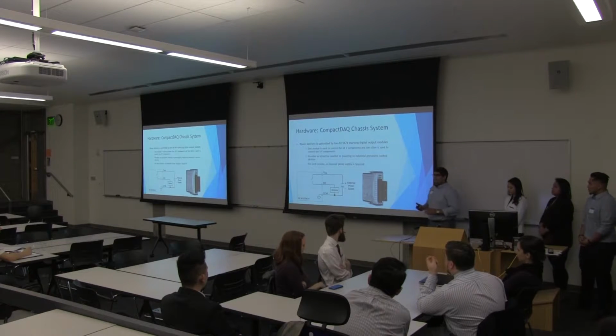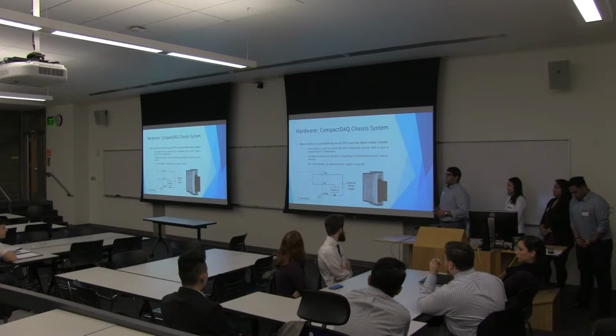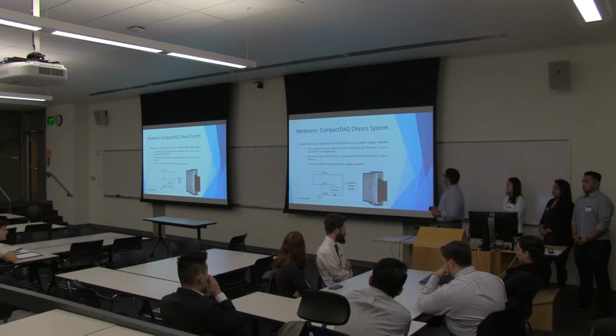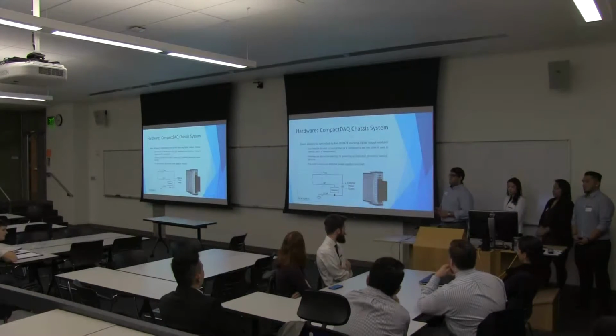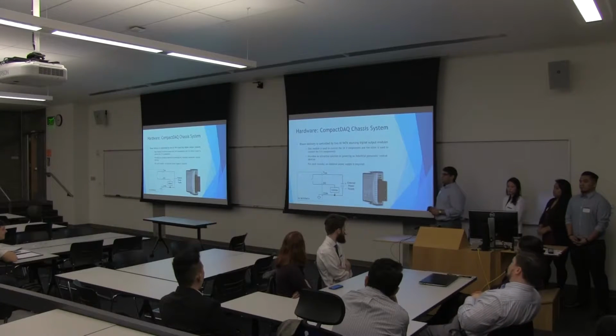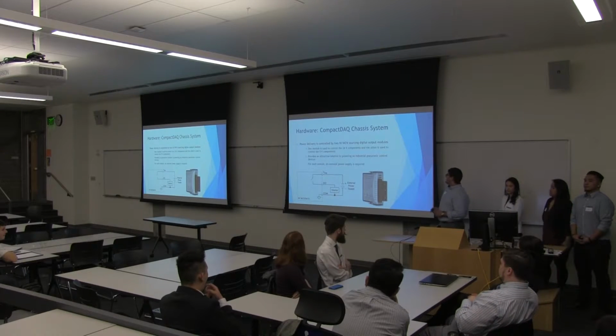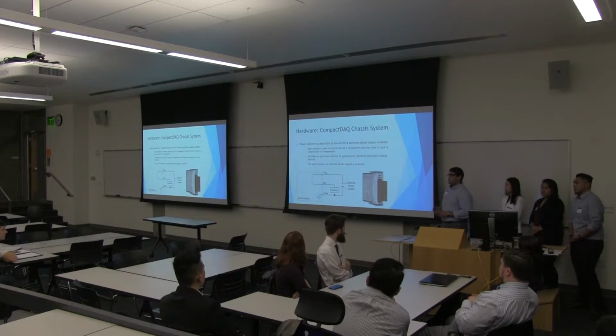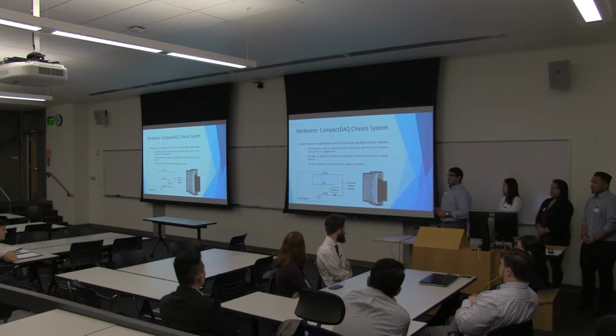The 2 power supply modules we use are the National Instruments 9474 digital sourcing output modules. These modules are used to power on our 24-volt and 5-volt devices in our system. These modules provide an attractive solution to powering on pneumatic control equipment, and each of these modules requires an external power supply. For our test fixture, we use both a 24-volt and 5-volt external power supply with each of these modules.